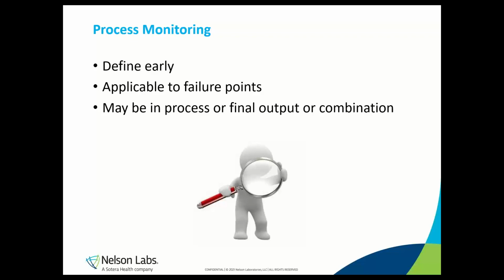ISO 11607 says that there should be a process monitoring, but it doesn't specify how to monitor or how often to do it. There's a lot of consideration that goes into deciding what are appropriate monitoring tests and intervals. If you have the equipment internally, it's easier to test more frequently, maybe with every production run or every day of production. You can also get results immediately, so manufacturing decisions can be made on the spot.